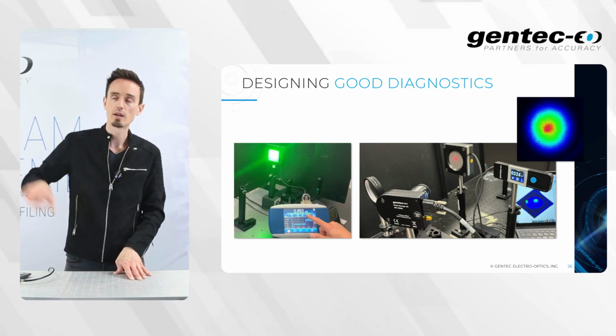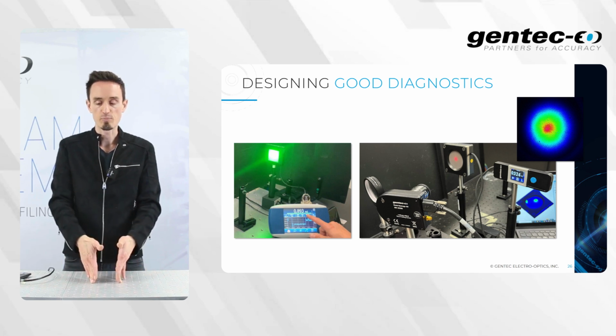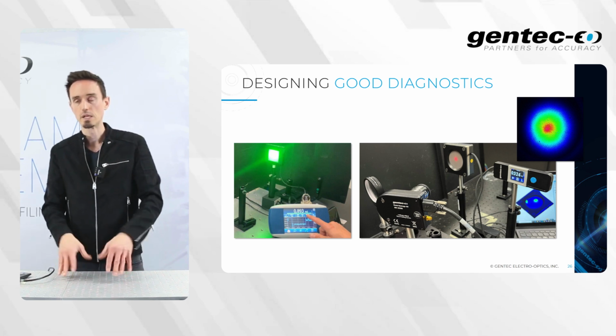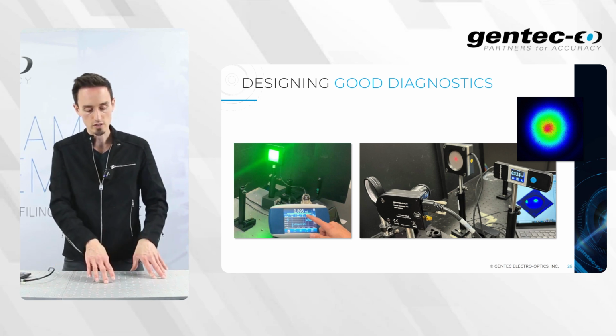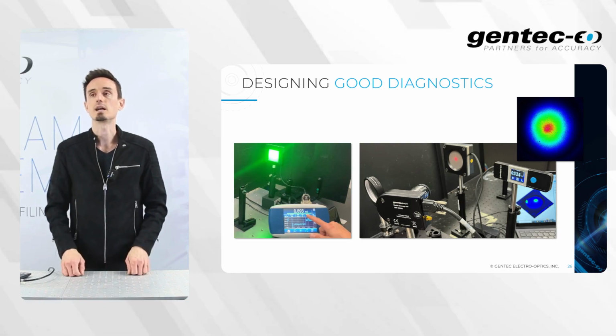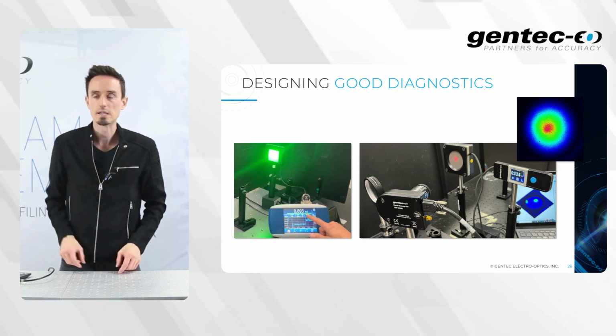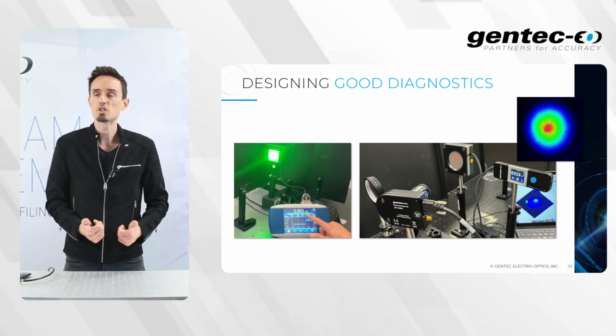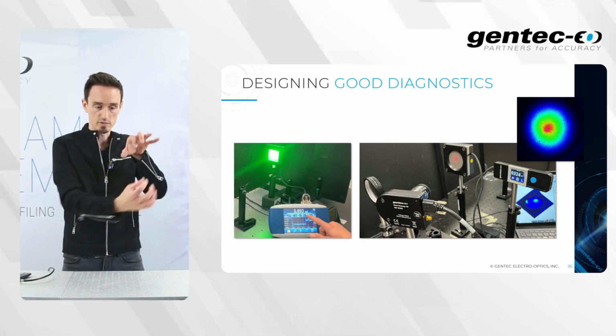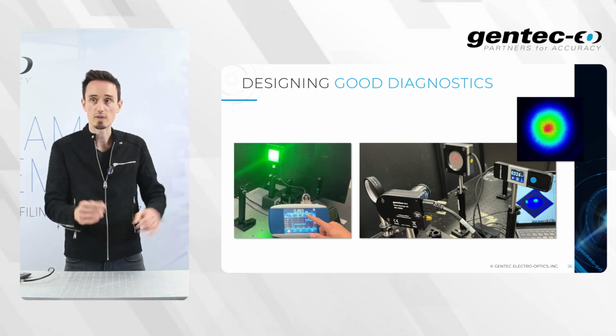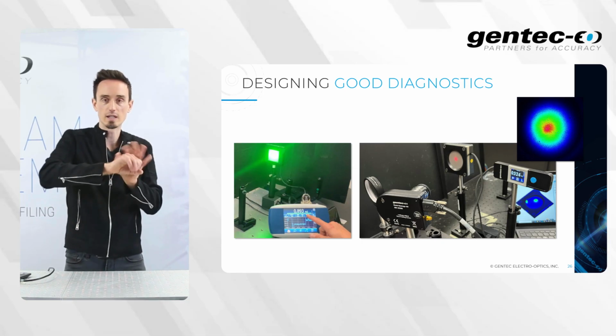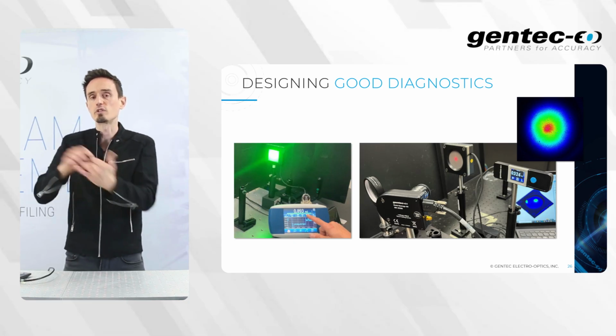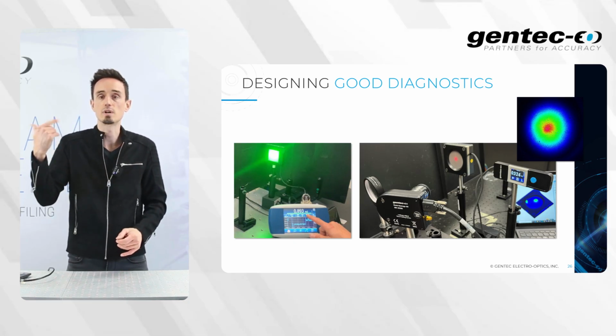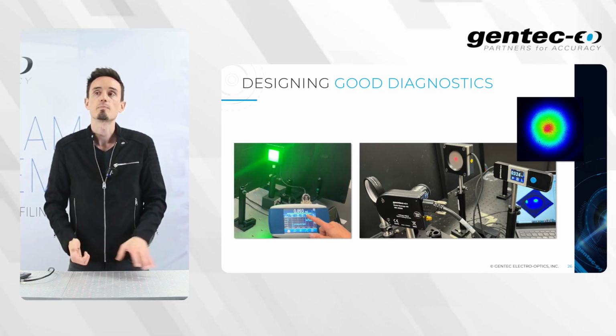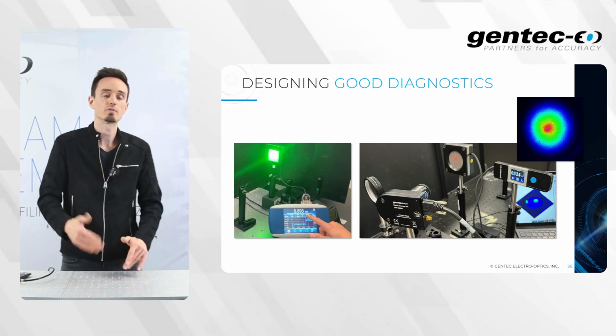And on the right side, you see a single pulse power meter calibrated for 5-second shots up to 10 kilowatts. That's the one, and you see the red spot grabbing all the beam energy, with a defocusing lens in front of it to make it safe, and then a beam profiler with a camera lens looking at the back reflection off the surface of the power meter to run safe inline both power and beam profile measurement in this case.